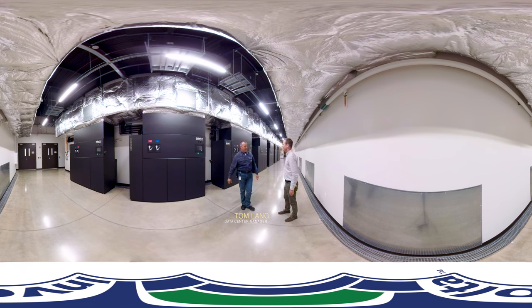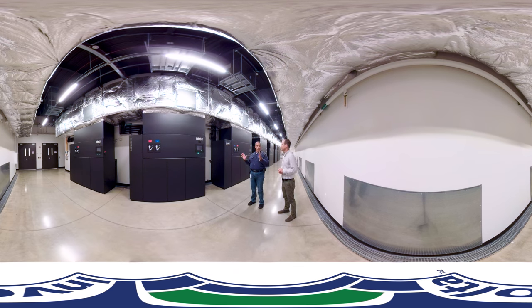Thanks for joining us today, Tom. Can you tell us a little bit more about the mechanical spine? Absolutely — it's a great space. This space houses all of our cooling that we need to generate, manage, and control for our data hall spaces. These CRAC units — which we also call computer room air conditioners — generate all of our cooling capacity, which we put into this plenum duct. This spans the back wall of our data hall; we duct through that wall and deliver the cooling from overhead through duct socks, which drops down and cools the spaces from top down. This ensures that our customers' equipment is taken care of environmentally at all times.